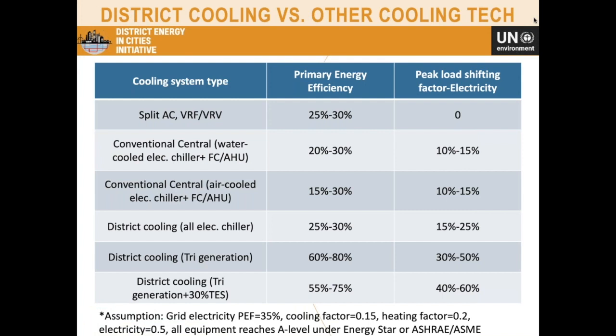This table shows a comparison between different cooling technologies, their primary energy efficiency, and peak load shifting factor. For split AC and VRV, primary energy efficiency is 25–30%. But using district cooling with tri-generation or thermal storage, you can increase this easily to 50–75% — almost double the efficiency. For split AC, you cannot shift the electricity peak load, but for district cooling — because of thermal storage and the diversity of cooling demand across different buildings — they have the ability to shift the electricity peak load by 30–60%.